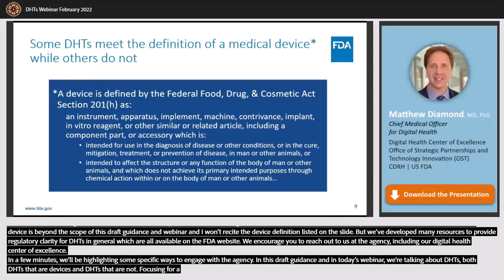The first question is whether marketing authorization, in other words, pre-market clearance or approval, is necessary to use a DHT in a clinical investigation. And the short answer is generally no. Devices intended only for use in clinical investigations are typically exempt from many requirements applicable to devices, including pre-market clearance or approval, as long as the investigation complies with applicable requirements under 21 CFR Part 812, which are the Investigational Device Exemption Regulations.